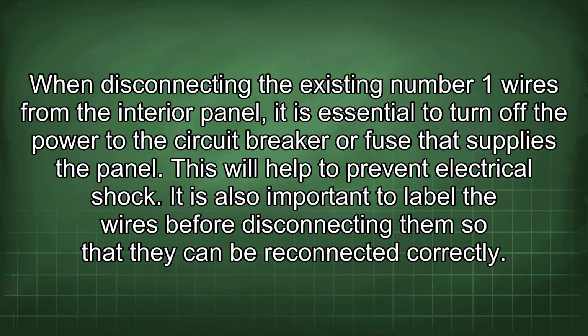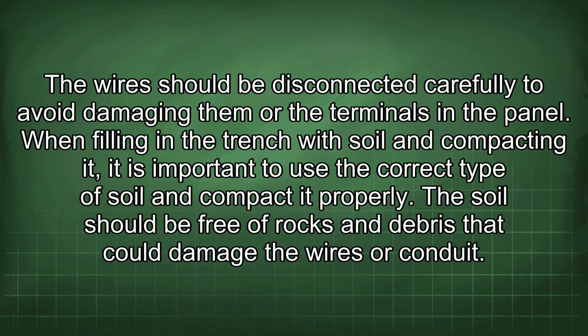When disconnecting the existing number 1 wires from the interior panel, it is essential to turn off the power to the circuit breaker or fuse that supplies the panel. This will help to prevent electrical shock. It is also important to label the wires before disconnecting them so that they can be reconnected correctly. The wires should be disconnected carefully to avoid damaging them or the terminals in the panel. When filling in the trench with soil and compacting it, it is important to use the correct type of soil and compact it properly.